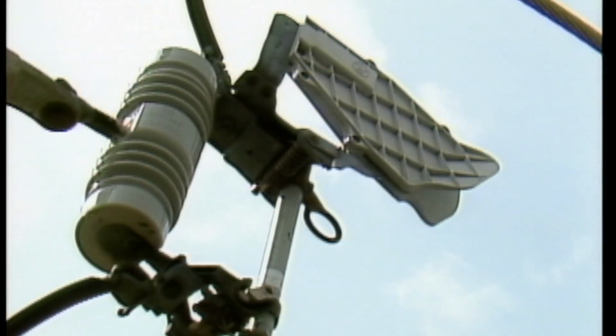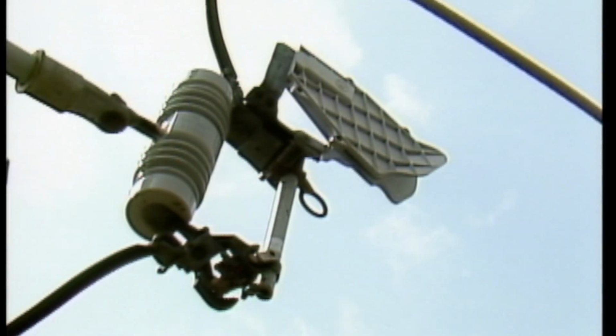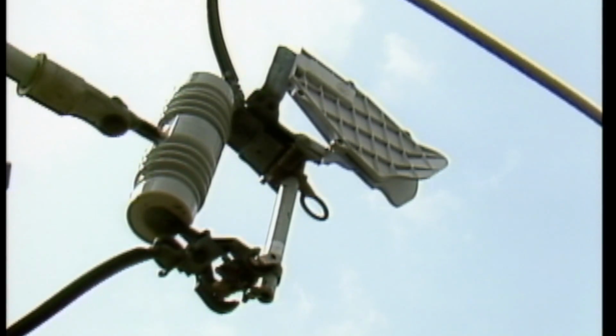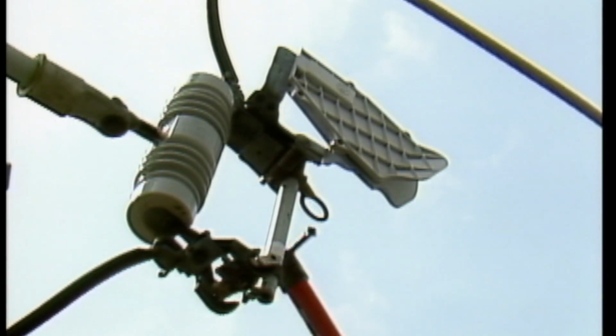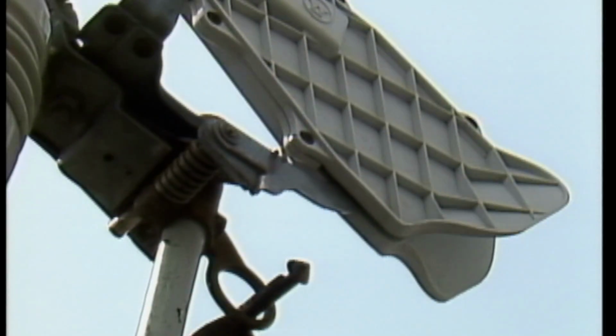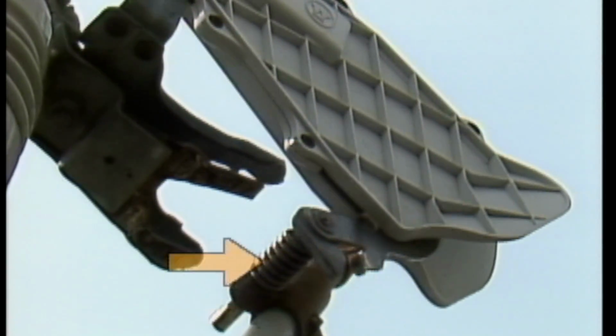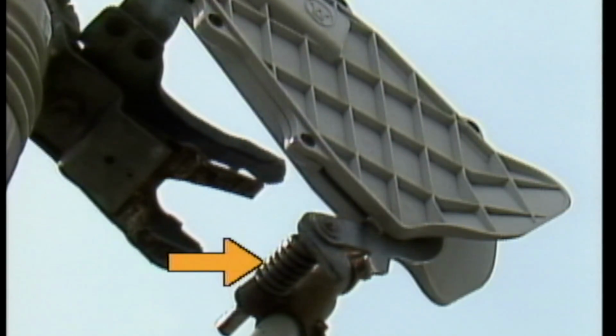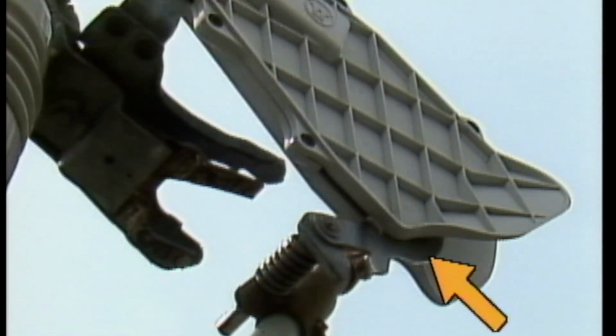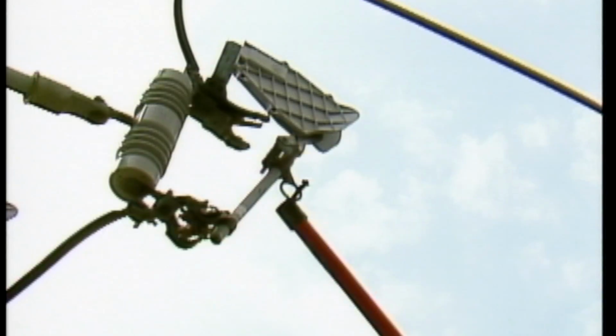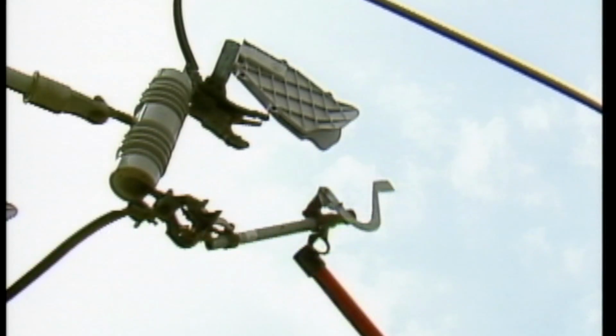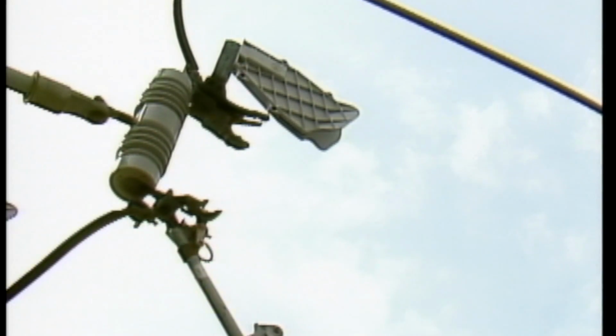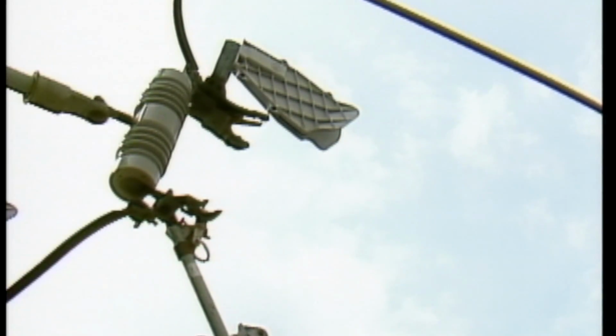This is an example of a load break cutout. It has a load break capability built in, and every time it's operated, the load break device is activated. Usually, this is accomplished through the movement of a spring. When the cutout door is opened, an arm maintains electrical contact until the fuse door clears the contact point. Then the arm is released from contact with such speed that the arc is quickly extinguished.